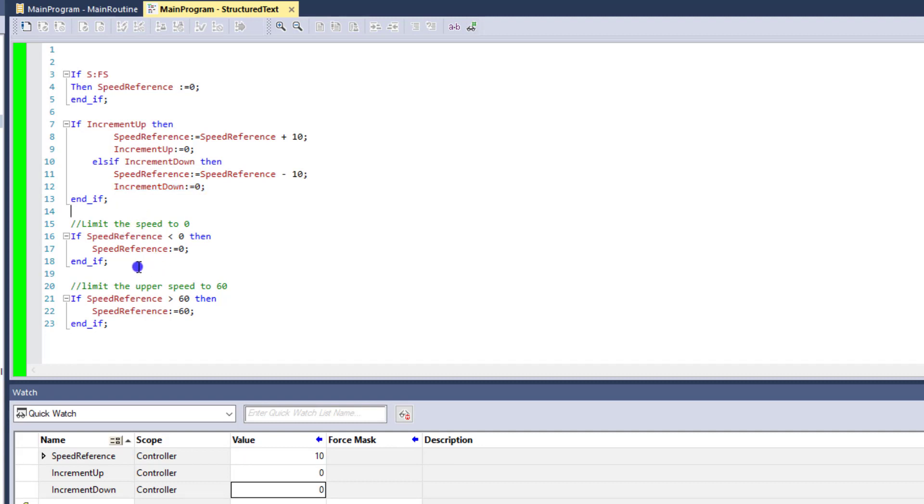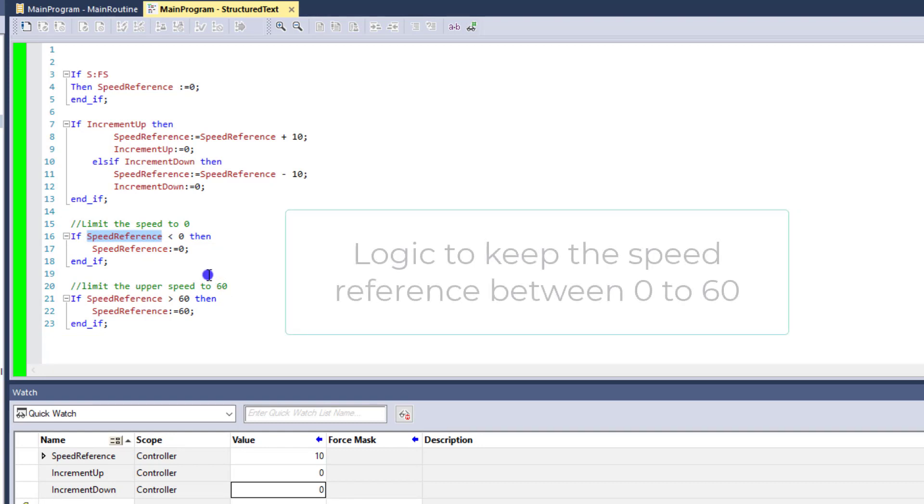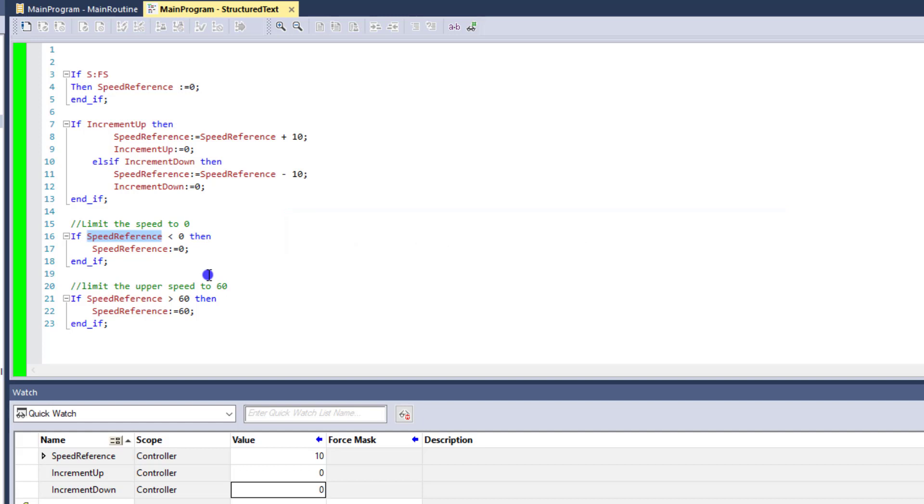Now, what I've done is I've added limits in here for the speed up and speed down. So, if the speed reference, this is to keep it like a safety mechanism so that it cannot take the, like if this was an actual drive for a speed controlling a conveyor, or something of that nature, let's just say it was deemed from 0, it could not go negative, it could not run backwards, so 0 was its final speed, and it could only move forward, but no faster than 60 hertz.